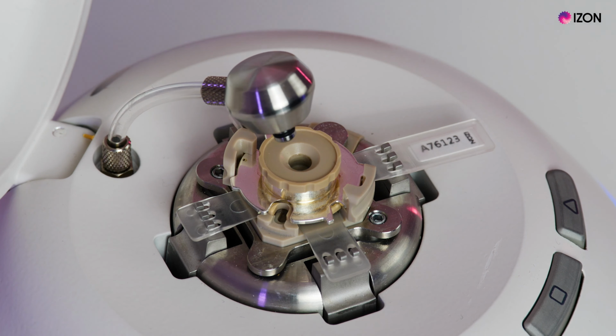Each measurement takes approximately 30 minutes, including calibration and cleaning of the nanopore between samples. Measurements below 100 nanometers can take longer if the user is required to intervene, as smaller nanopores are more prone to blockages than larger ones. Once complete, the user can choose to continue on with further measurements or can choose to finish the measurement and clean the system. Data processing is performed on Izon's Data Suite software, which intuitively selects only the calibration files for data that has identical measurement parameters, ensuring users' data is accurately calibrated for precise results.